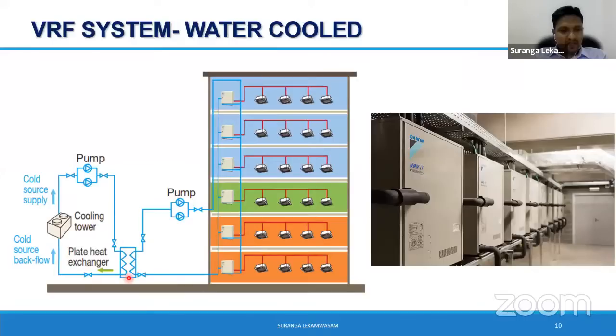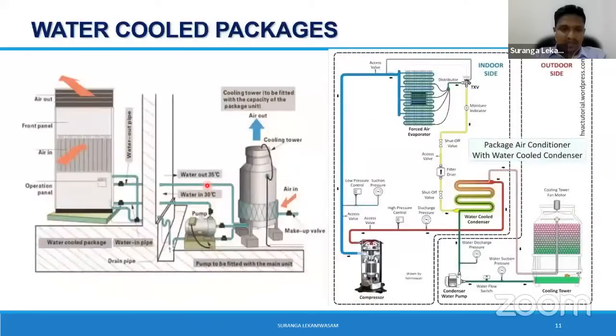It looks like this. If you want to go for a closed circuit, you can see this is your condenser loop. The condenser water is cooled by a separate cooling tower circuit, which is called a closed loop system for condenser water. But again, the system efficiency is somewhat compromised, because if you produce, let's say, 30 degree condenser water, then the condenser circuit may be a little higher than that. So that will somewhat compromise the efficiency. But yes, you can think of installing it also. This has been addressed by some manufacturers, and they have gone for a sort of shell and coil heat exchanger instead of a plate heat exchanger now, and are trying to go with an open cooling tower circuit, right? So this is another option which you can look at.